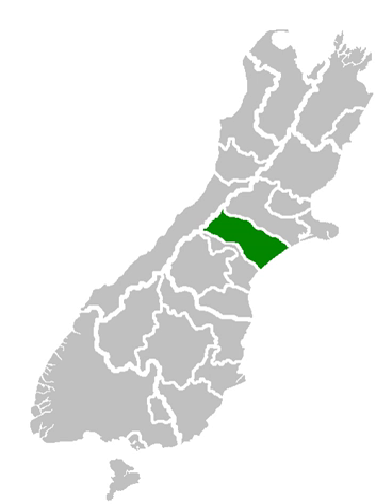43.7507 degrees south, 171.8460 degrees east, -43.7507, 171.8460 Transpower Thompson's Track substation. The proposed substation would connect to both the Livingstone to Islington line and the nearby Tekapo B to Islington 220 kV line via a short tie line and have two 220/66 kV transformers, one new and one relocated from the Ashburton substation.